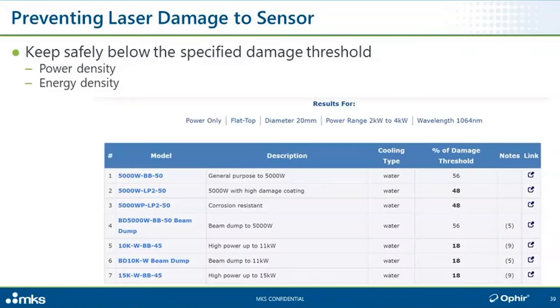So if we look at an example of an output screen from the Ophir sensor finder, we see that for each sensor that comes up as a potential solution, one of the pieces of information the sensor finder gives you is how far you are under these laser conditions that you entered, this power, this beam size, whatever, how far below the damage threshold are you? So in this case, for example, all other things being equal, this sensor at the laser conditions that I entered would be operating at 56% of the damage threshold, this sensor at 48%. Not a huge difference, but all other things being equal, I'll probably prefer to choose this sensor.